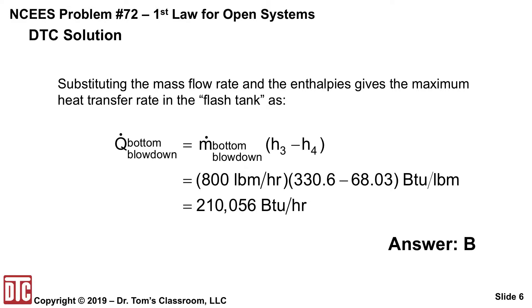Now we can take that information — M-dot of 800 pounds per hour times the difference in enthalpies H3 minus H4 — to get a little over 210,000 BTUs per hour, and that's answer B. I hope that helped clear up some of those unfamiliar terms. As always, we appreciate you allowing us to help you prepare for this exam.